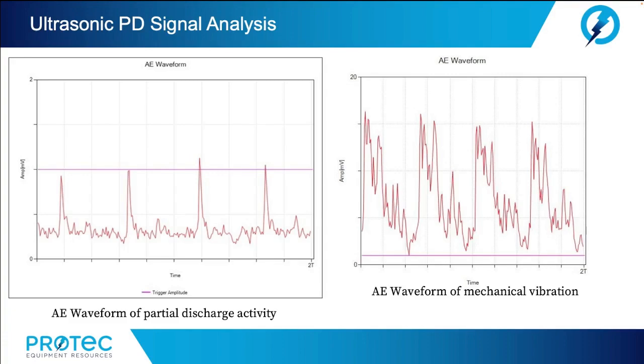with phase timing. Finally, the most competent way to be sure if you have a partial discharge or a vibration is to compare the ultrasonic signal with the high-frequency CT or UHF signals simultaneously. For this, you need a multi-channel diagnostic unit to see the relative timing of ultrasonic and electromagnetic pulses. If the ultrasonic emissions are in perfect synchronization with the high-frequency CT pulses and the UHF pulses, then it must be partial discharge. Vibration will not produce electromagnetic pulses.